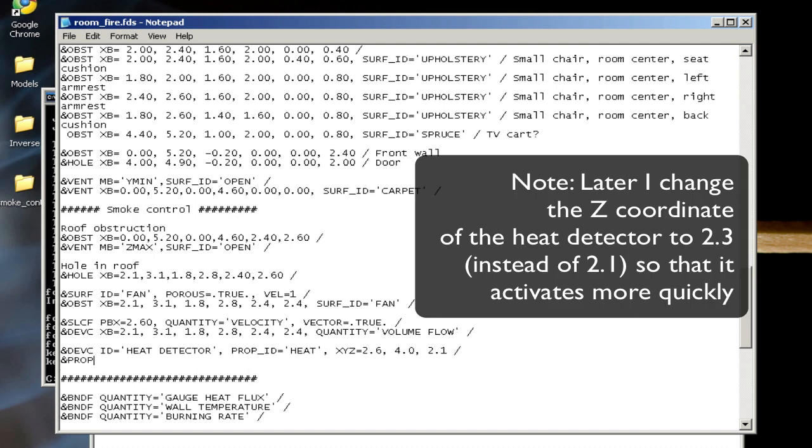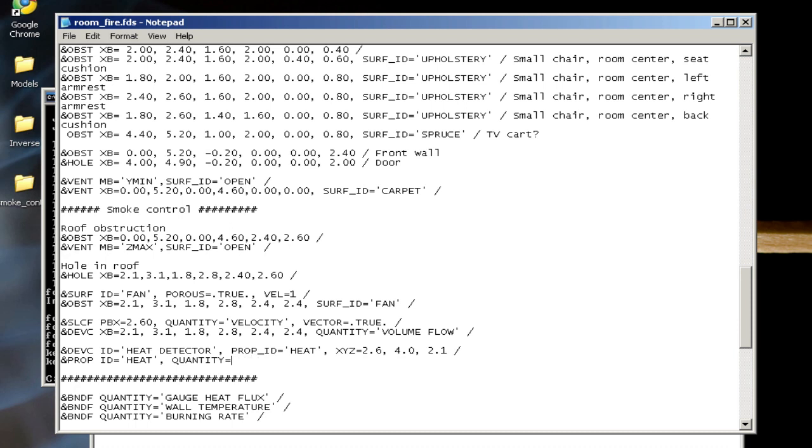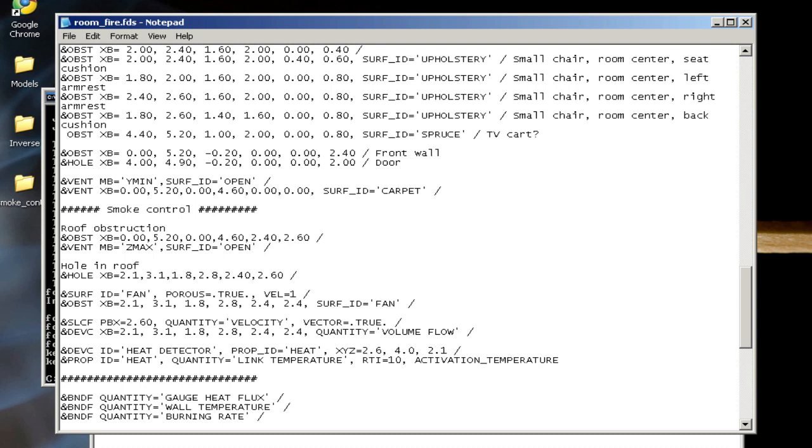I also need to add in a prop line with an ID that matches the prop ID on the previous line. So heat, quantity equals link temperature. RTI is a response time index—I'm going to set this really low for now, just so I can get quick activation of that heat detector. Then I'll set the activation temperature to 30 degrees Celsius, again a very low temperature for a heat detector, but I want to activate quickly for this demonstration.